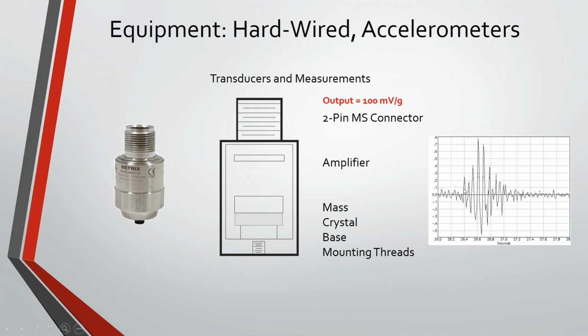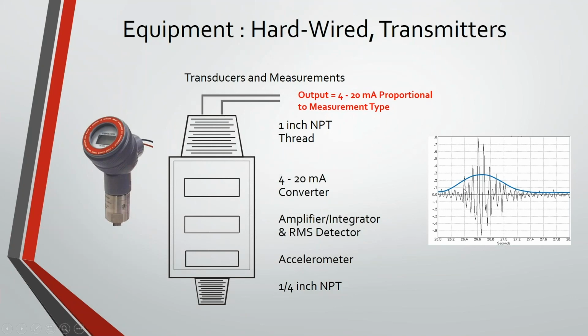So what's the difference between a sensor and a transmitter? Well, a transmitter takes that same accelerometer signal from the bottom of the housing and sends it through an integrator and an RMS detector. In this case, we're integrating to get velocity, and the RMS detector is going to give us the level of that velocity vibration. Now instead of this black line, we're looking at the blue line. That's our level measurement.